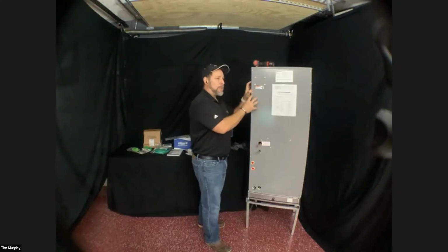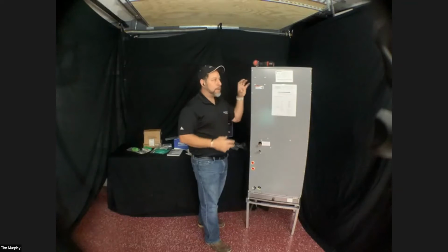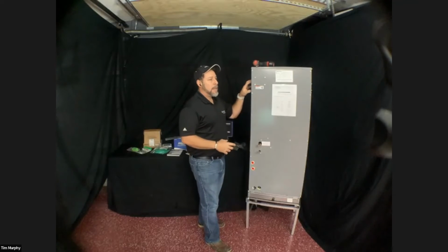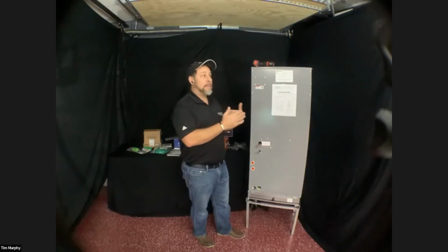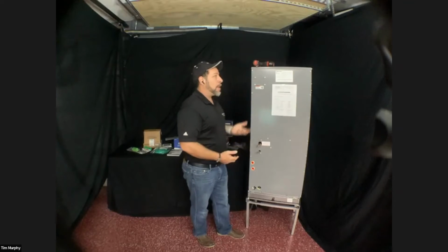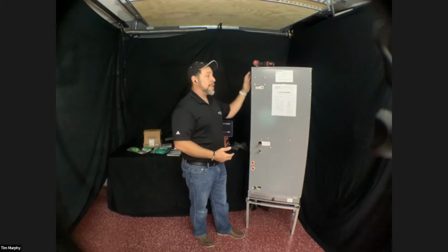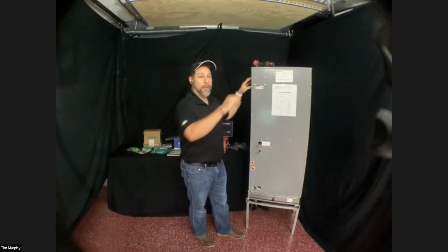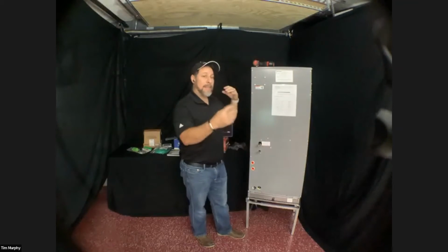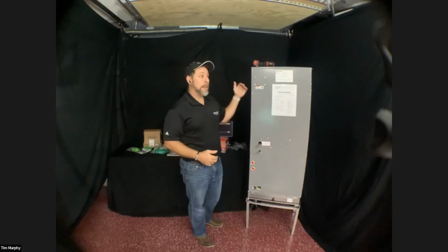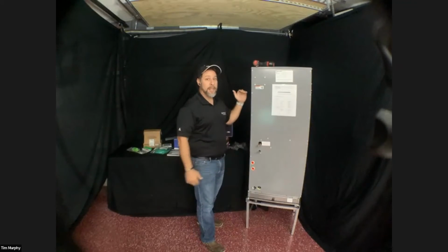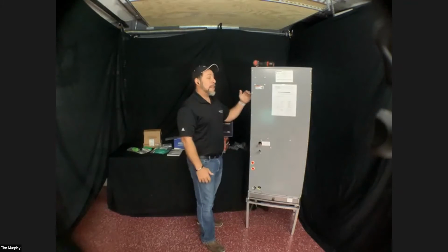If you get a spike or drop in voltage, what could happen is that voltage that's incoming to this unit is going to impact the DC voltage in the communication. So if you get a rise in voltage, and say this is sitting at 210 or 212, and the outdoor unit is sitting at 208, that DC voltage that's communicating back and forth is not going to be correct. So you could, and you will most likely in that situation, get a communication error code that may disappear when you get there to go look at the job.